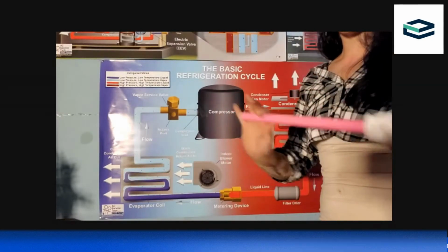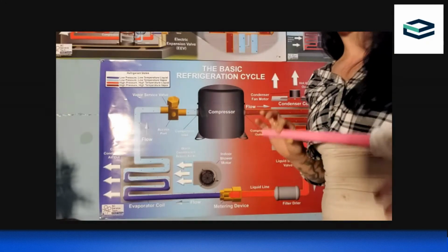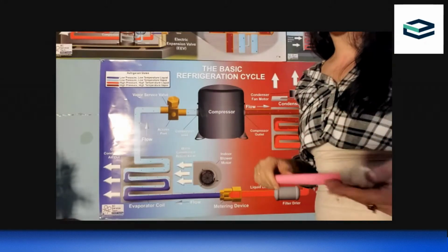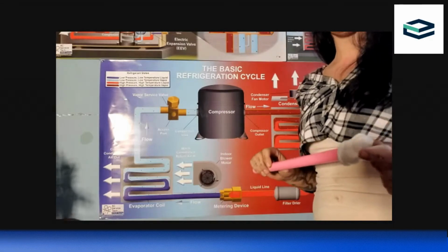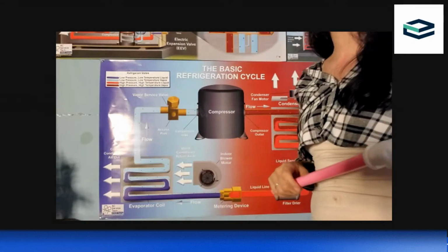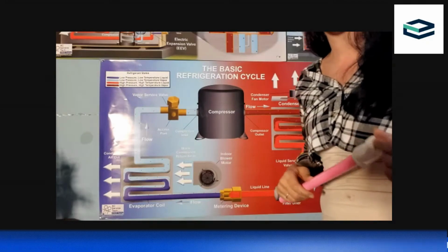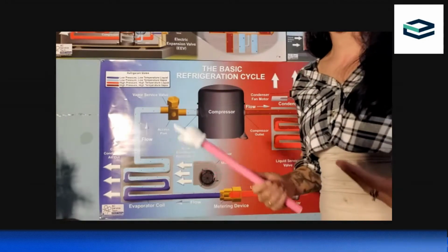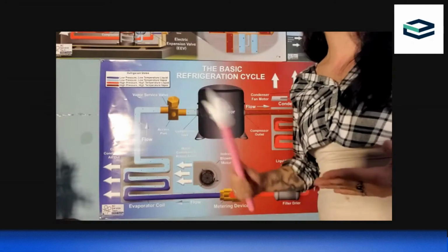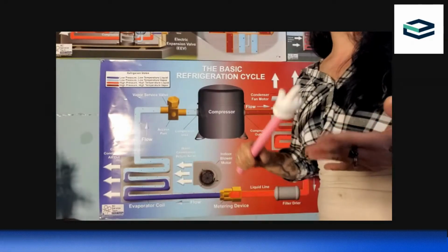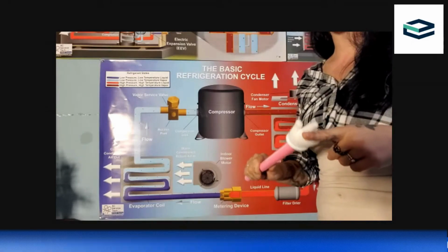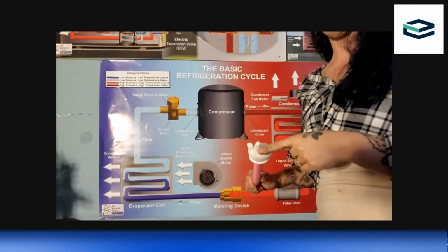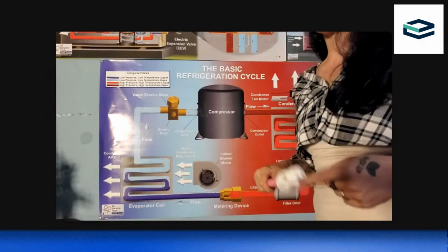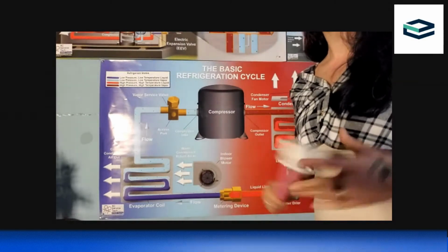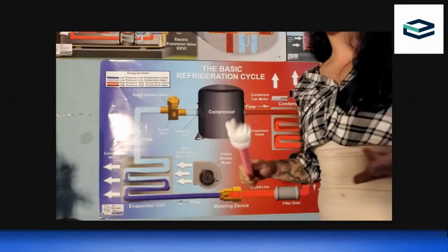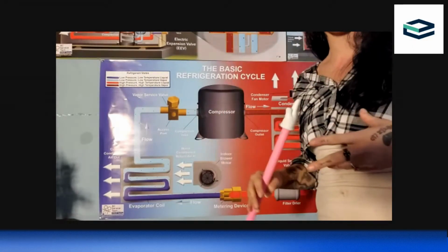But these refrigerants are harmful to the environment, basically. So we started out with R12 and R11, which were CFCs, chlorofluorocarbons. We found out one molecule of chlorine in the atmosphere actually eats and disposes of over 100,000 ozone molecules. Ozone is 3 oxygen molecules. So for every 1 molecule of chlorine in our atmosphere, it was eating over 100,000 ozone molecules, which is what caused, you guys have heard about it a million times, I'm sure, the hole in the ozone. Not exactly a hole, but an opening in our ozone that protects us.